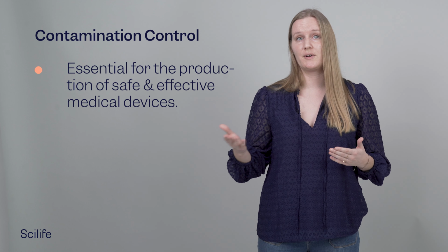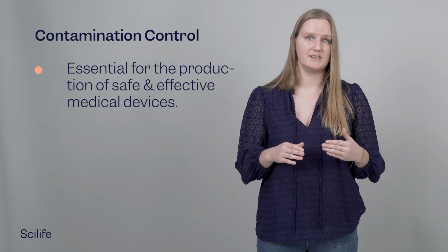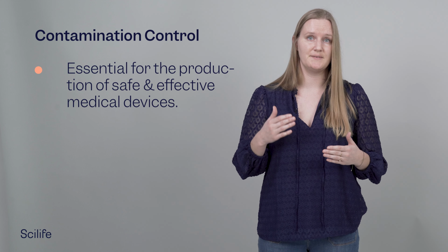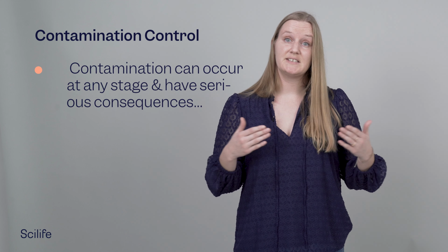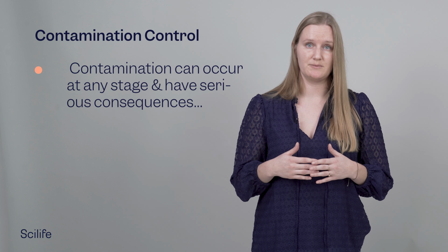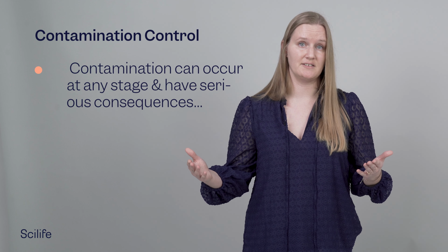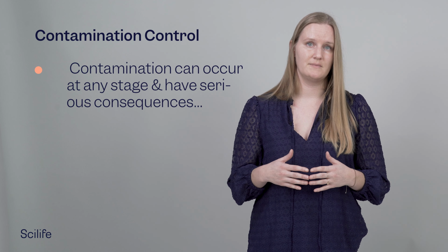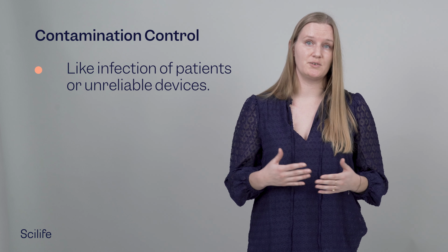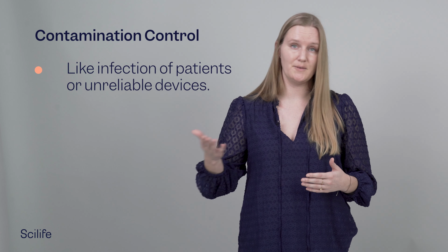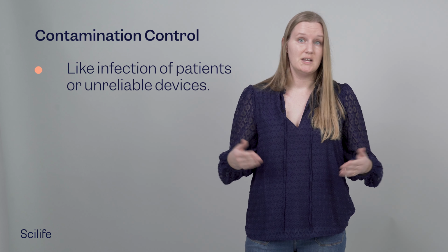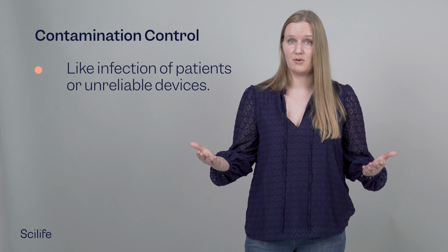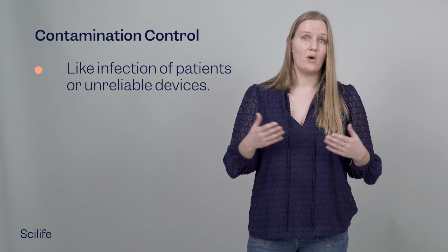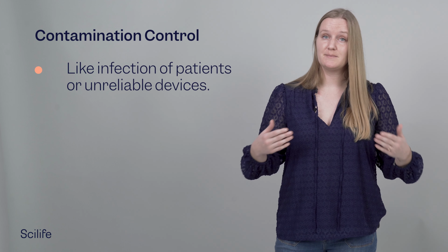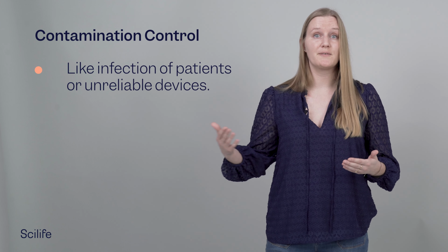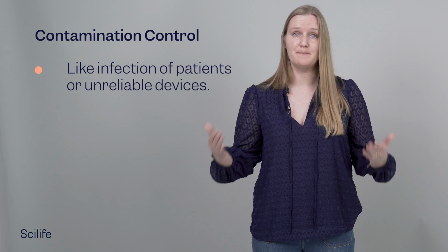According to ISO 13485, contamination control is important because it is essential for the production of safe and effective medical devices. Contamination can occur at any stage of the production process, from raw material and components handling to finished product packaging. And it can have serious consequences for the performance and safety of the medical device. For example, contamination with bacteria or other microorganisms can lead to infection or other adverse reactions in patients. Similarly, contamination with particles or other foreign matter can affect the performance or reliability of the device.